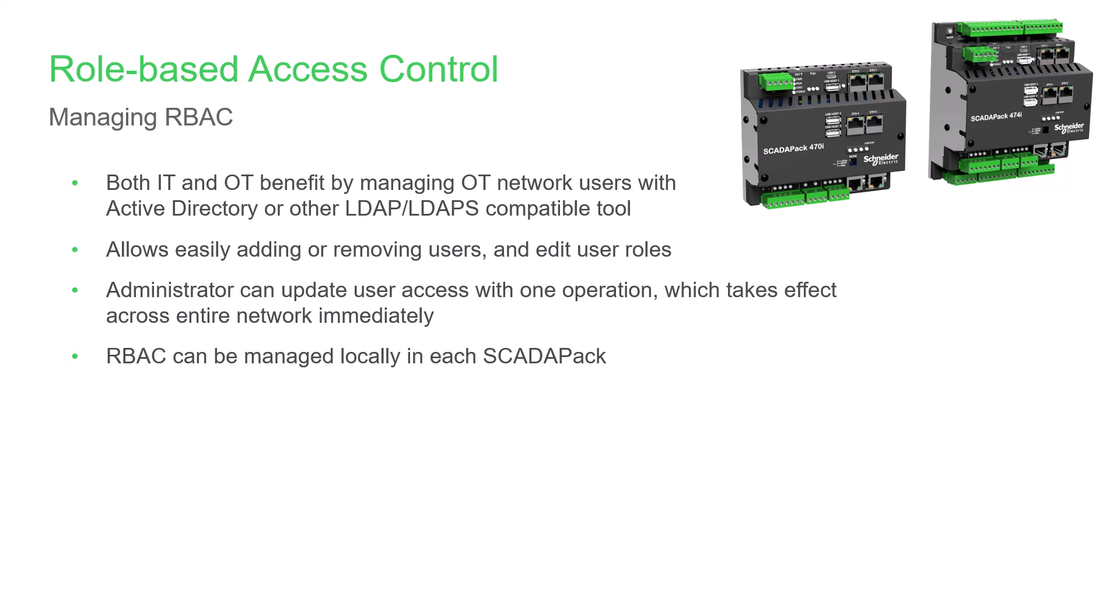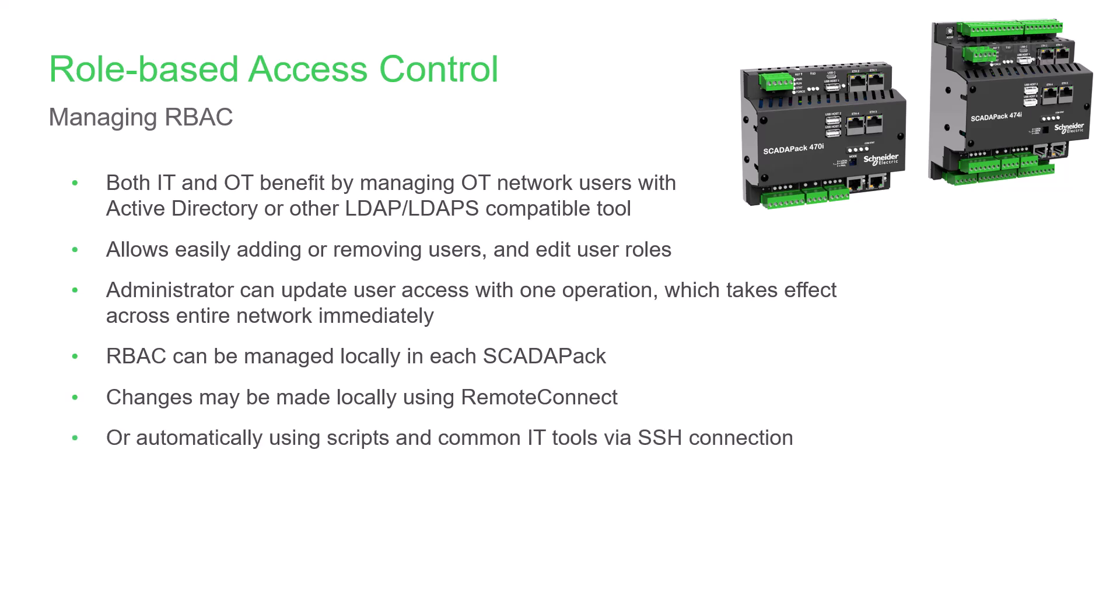You can also manage role-based access control locally in each SCADAPack. You can change local user configurations locally using Remote Connect, and automatically using scripts and common IT tools provided by CyberArk, SolarWinds, or others, through an SSH, or SecureShell, connection. This also ensures a local account is available if telemetry issues occur and you need access when on-site.